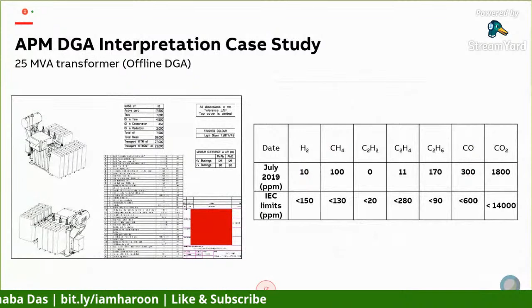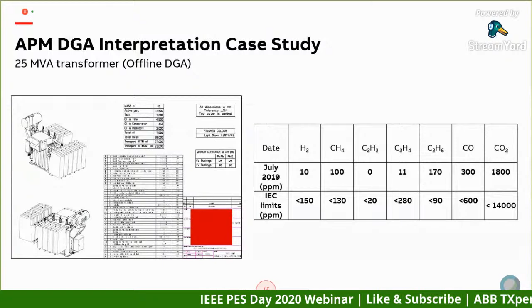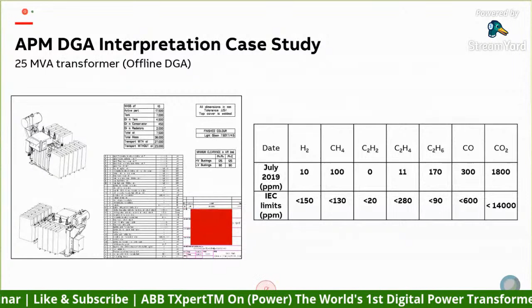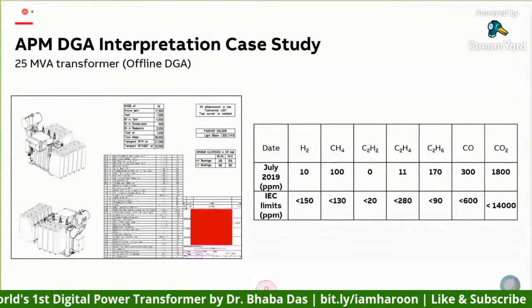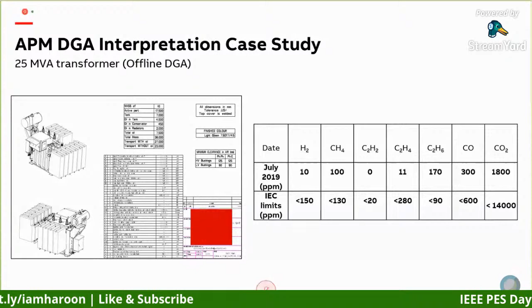So I'll give you a quick example of DGA interpretation. We had a transformer where we got offline DGA data, and then we got the lab test results. What we did is we checked against the normal IEEE limits. The lab results gave us this answer saying that we have a problem. The DGA indicates there is a thermal fault, and all it did was recommend further monitoring to establish trend and resample in 6 months' time.